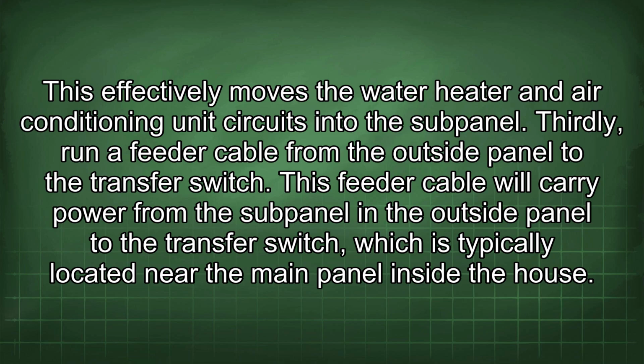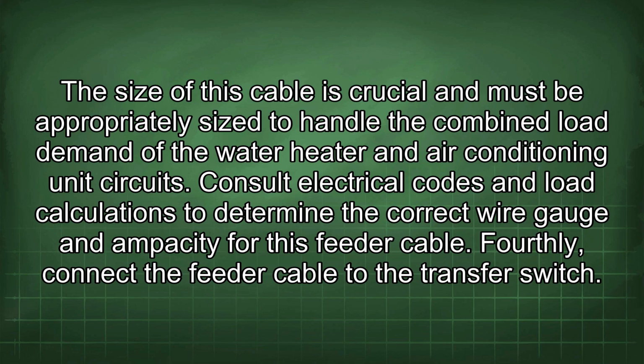Thirdly, run a feeder cable from the outside panel to the transfer switch. This feeder cable will carry power from the subpanel in the outside panel to the transfer switch, which is typically located near the main panel inside the house. The size of this cable is crucial and must be appropriately sized to handle the combined load demand of the water heater and air conditioning unit circuits. Consult electrical codes and load calculations to determine the correct wire gauge and ampacity for this feeder cable.